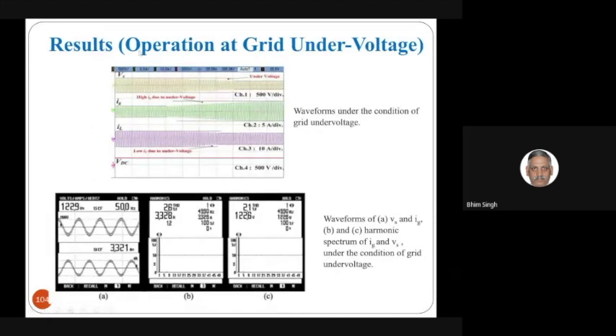And this is for under voltage. When voltage reduces, still the system works very well. Otherwise, the earlier system was tripping with under voltage and over voltage, when protection was put in that way. But here the control is modified in a manner that it can work with under voltage as well as over voltage without any problem. There is no changeover. And the THD here in the under voltage is also only 2.6% for the grid current.